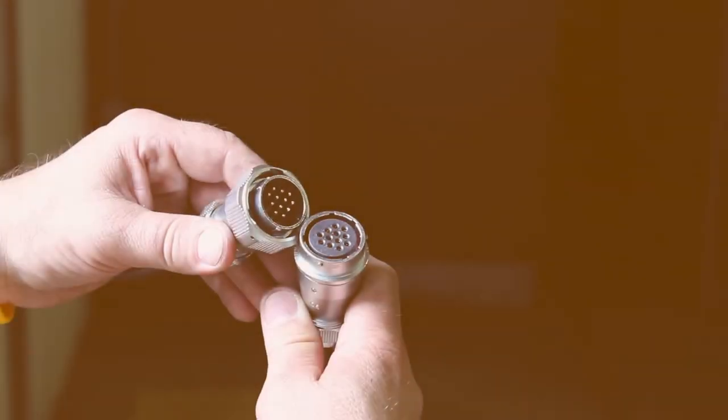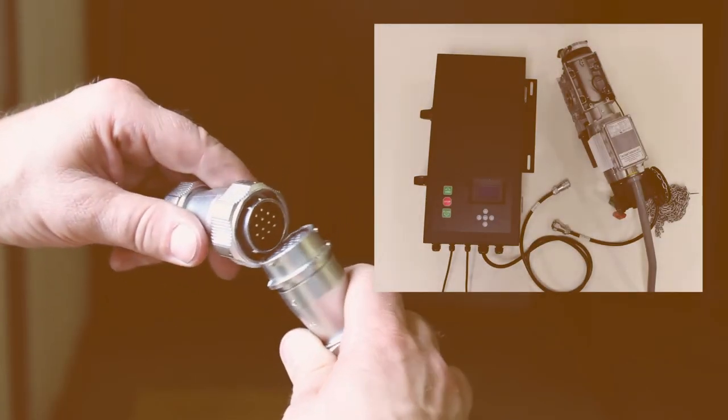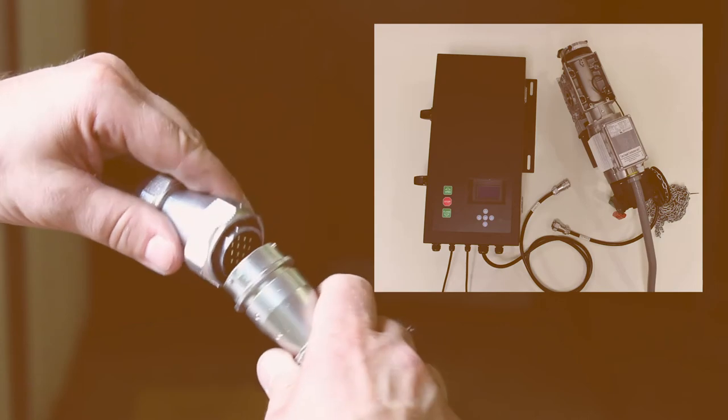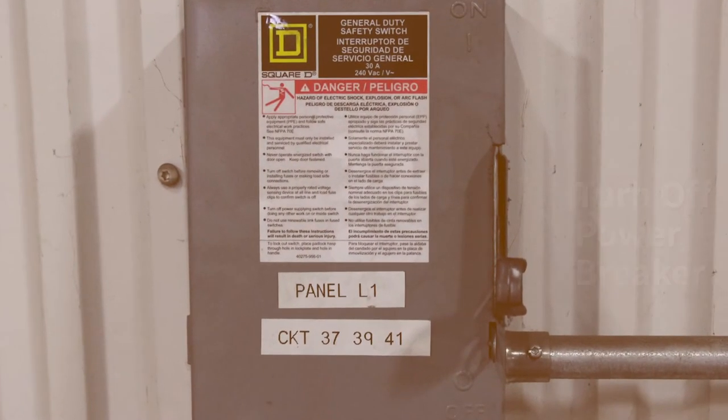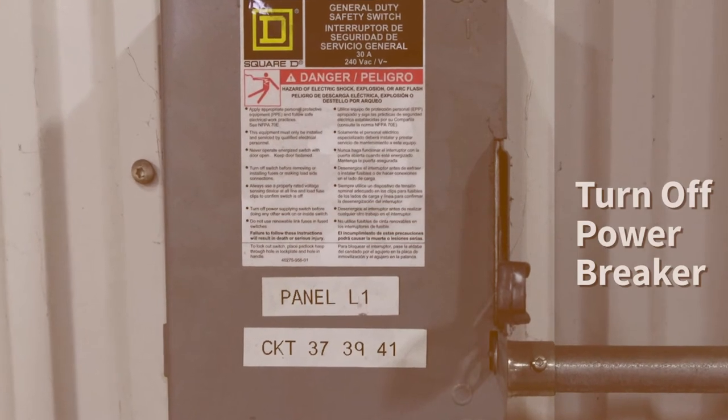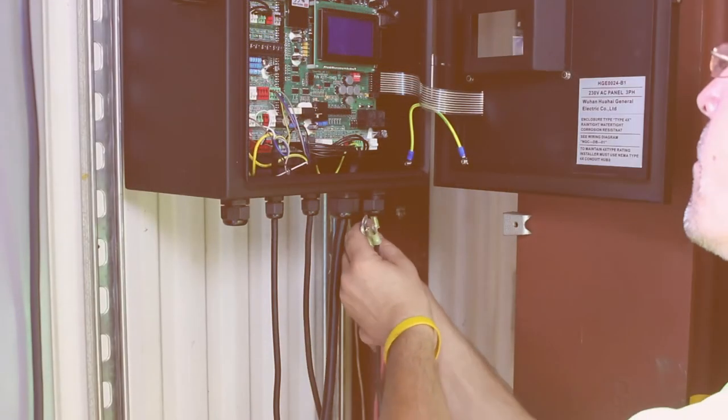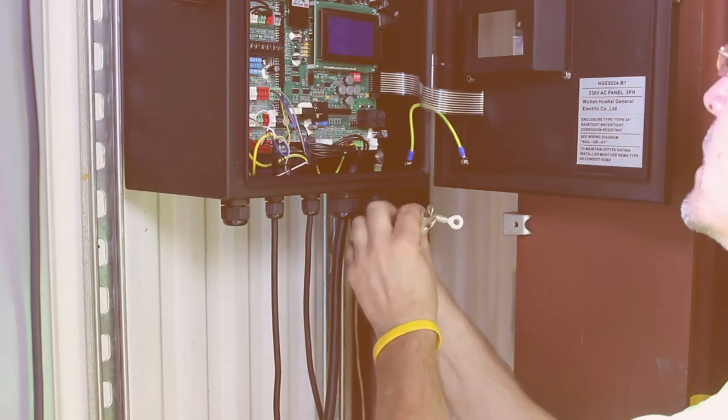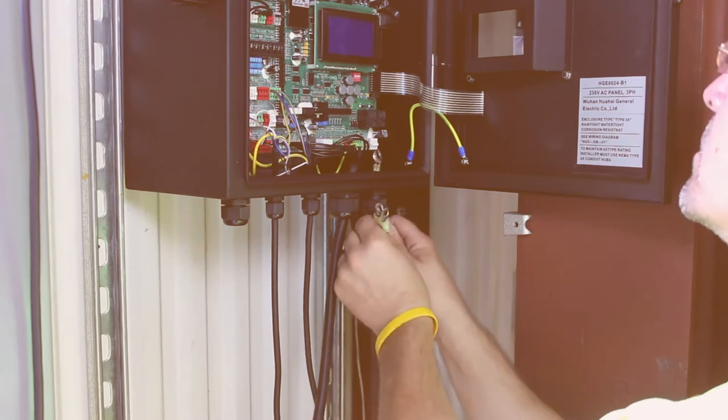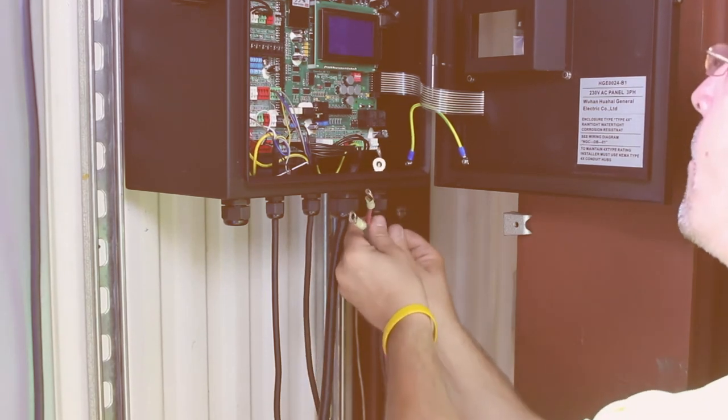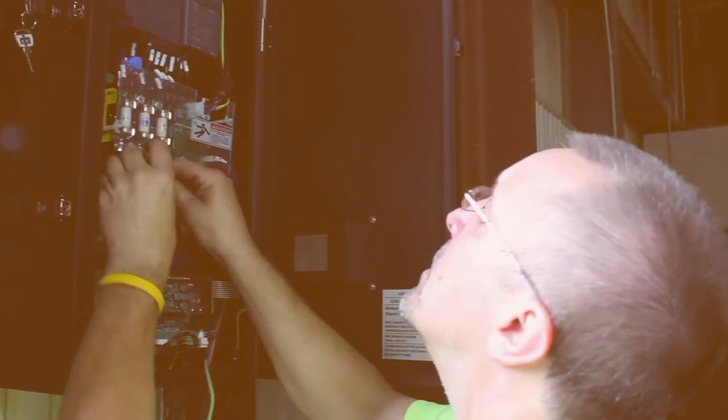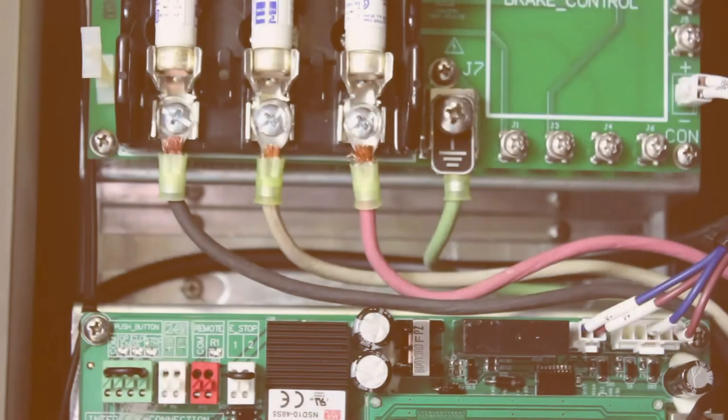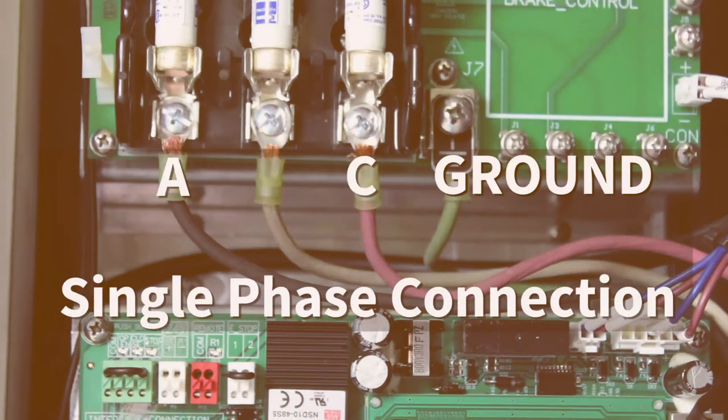Now we're going to connect the incoming power. First, turn off the power breaker. One, run wire into the panel using one of the two pre-drilled holes located at the bottom of the control panel. Two, route the wire down the side of the control panel. Three, for a single phase connection, make connections to the A, C and ground terminals.